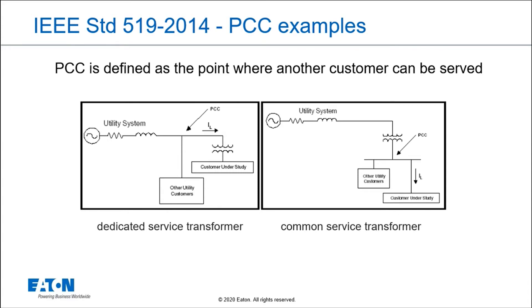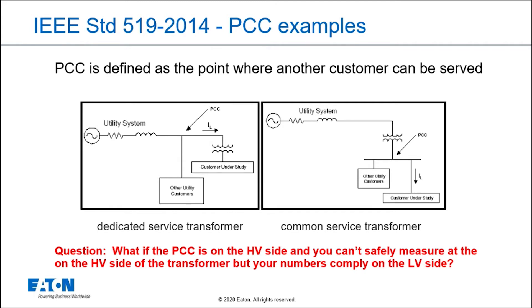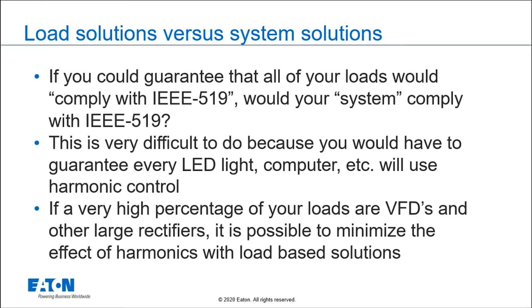A lot of times people ask: what if I have to check voltage distortion and current distortion on my transformer, but I don't own the transformer and the utility wants me to check it on the primary? Well, if you pass the distortion levels on the secondary, you're going to pass on the primary. Harmonic currents come from the loads, so if you're putting harmonic currents on the system, the current goes through the transformer — except for some third harmonics, triplens — so current distortion on the primary and secondary should be about the same. Voltage distortion will be less on the primary than on the secondary, because the transformer impedance is one of the bigger parts of the system impedance.